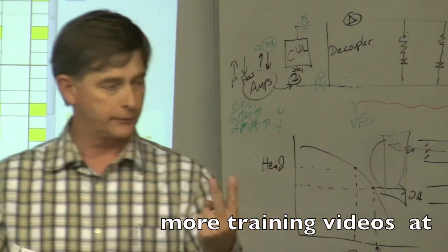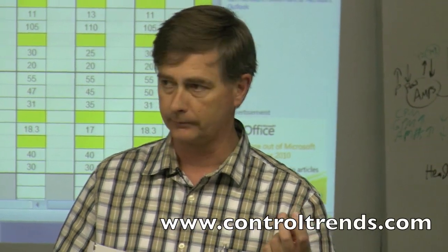How do you calculate condenser approach? Approach is the difference between your leaving temperatures, water, refrigerant. All right? It's whatever temperature it is. It's on the condenser, it's on the condenser side. Chill water approach is on the chill water side.